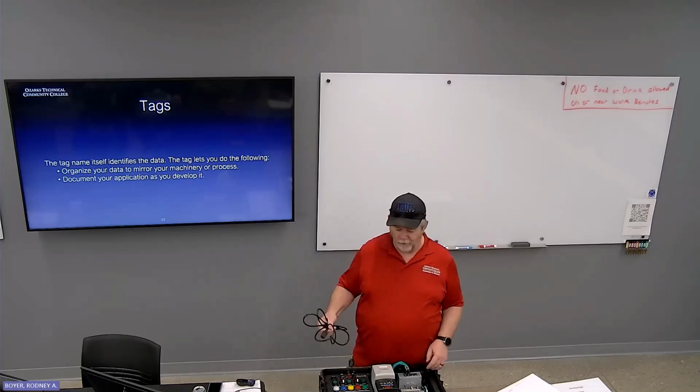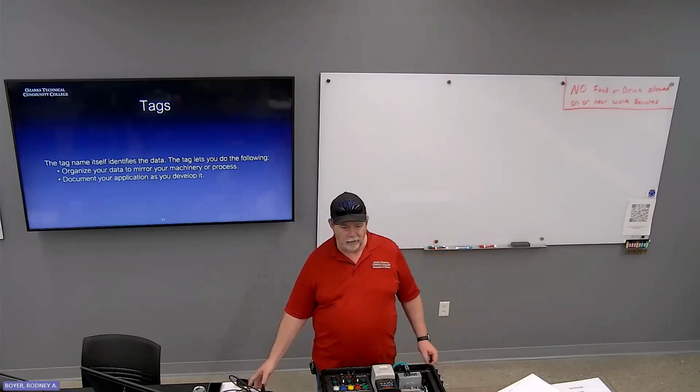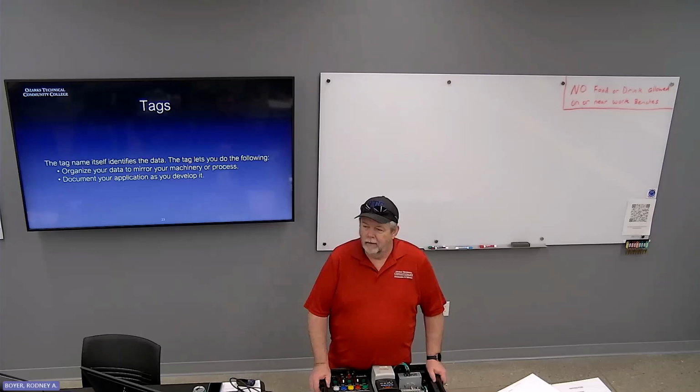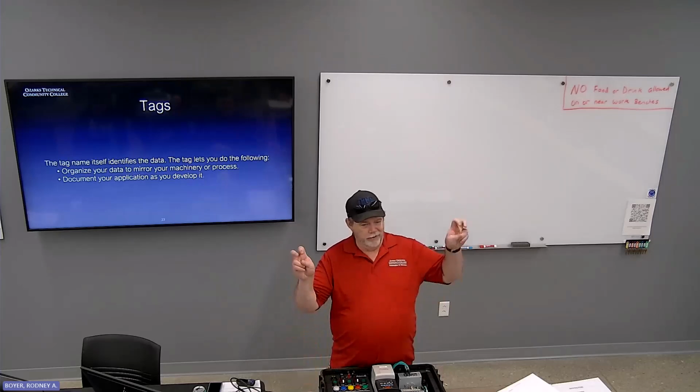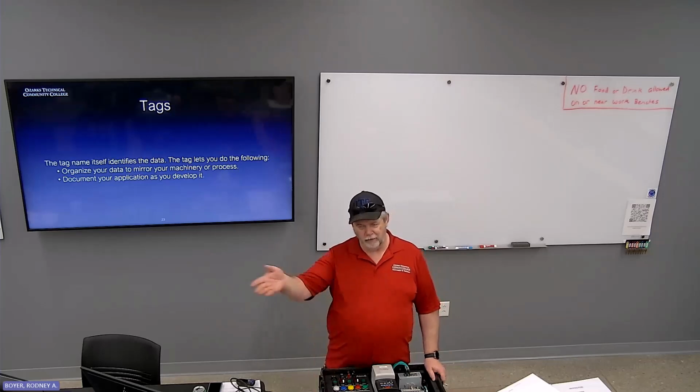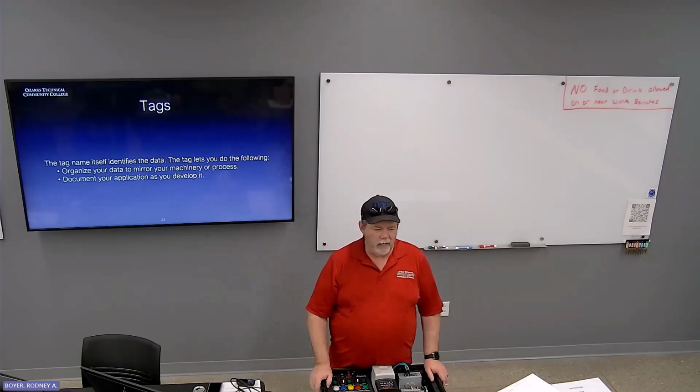If you need a fault reset switch, you call it fault reset switch. Okay? So you can easily see, whenever you're looking at your logic, that in order to get conveyor 1 to turn on, you have to have the emergency stop. You have to have the stop push button probably. And then the start push button will allow your conveyor 1 to energize, and that of course will latch your start push button so you can let go of it.